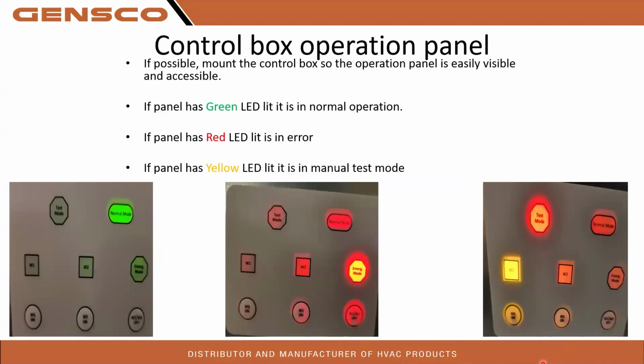Control box operation panel. So that little panel on the outside of that box. We talked about it a little bit earlier, but I'm going to go into more detail now. Make sure that that little panel is accessible if you can. Make sure to point it out to the customer in an easily seen spot. Make it conspicuous, because it will tell you quite a bit of information, believe it or not, with just a couple of LEDs that it has. So if you're using a 24-volt thermostat and your IntelliHeat controller is in error, this is the only way the customer is going to know that. Otherwise, they may be running gas heat without even realizing it. They're not running the heat pump because there's an error on the system. I see that fairly often on 24-volt controls, customers complaining, hey, my furnace always seems like it's running the gas. It doesn't seem like it's running the heat pump.